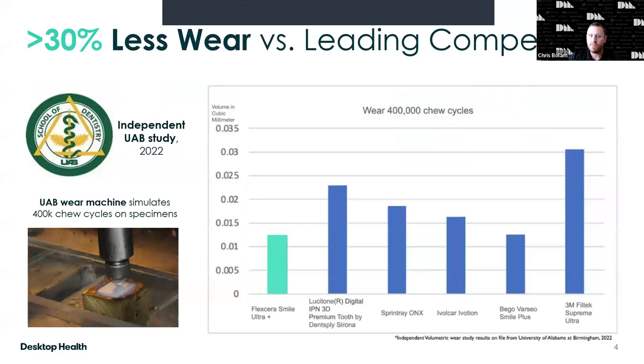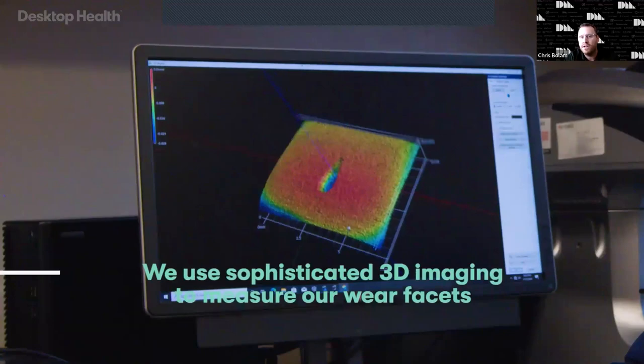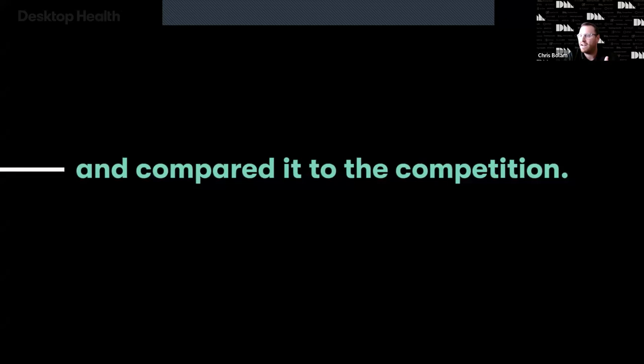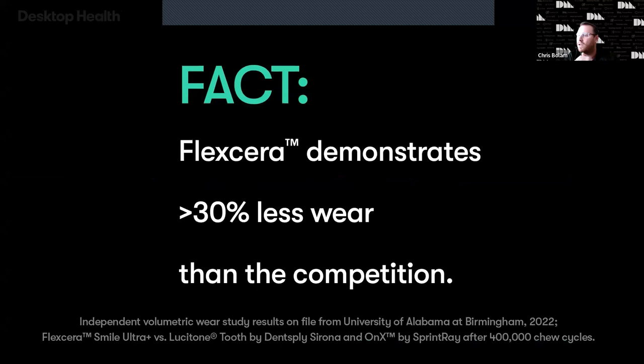An independent wear study was done in 2022 by the University of Alabama, taking similar printed resins through a wear cycle simulating 400,000 chewing cycles. The small numbers indicate less wear over that cycle. They take devices simulating wear in the mouth under moisture, then take an overlay with a scan to measure volumetric reduction. Flexcera performed really well there — very little material was removed during testing. Wear is very important when talking about denture teeth.